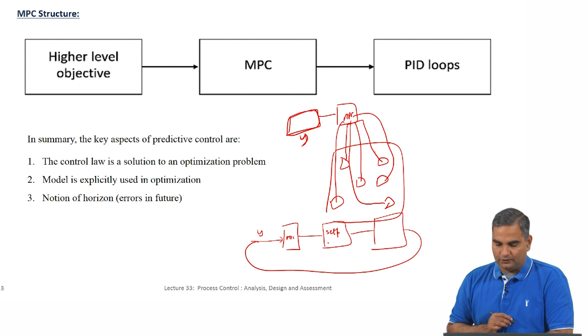There are several advantages to implementing MPC like this. Number one is that all the advantages that you have got out of implementing PID, you do not take out and remove, because the PIDs are still in place. So whatever work you have done till now is all in place, and of course if there are some safety critical loops that require pure safety related attention, it is very difficult to bring that into an MPC framework, because you have to again look at each individual loop and see whether the objective is to do with safety, or performance and so on. So all of those kinds of details can be relegated to a lower level PID control loop or loops, and MPC can really focus on getting something more than what the PID loops are doing in terms of higher level performance objectives. So, that is one reason why the PID loops are there.